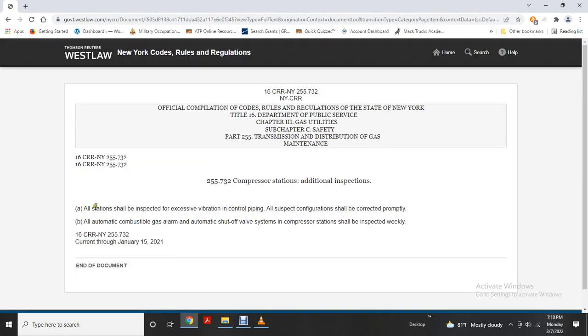Compressor station additional inspection. All stations shall be inspected for excessive vibration in control piping. All suspect configurations should be corrected properly. All automatic combustible gas alarms and automatic shut-off valve systems of the compressor station should be inspected weekly.